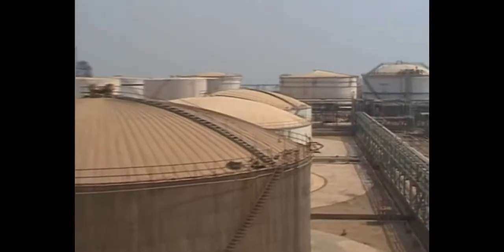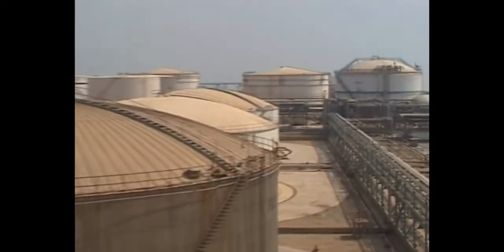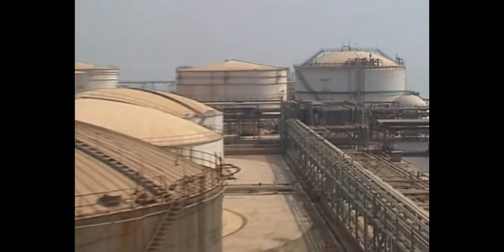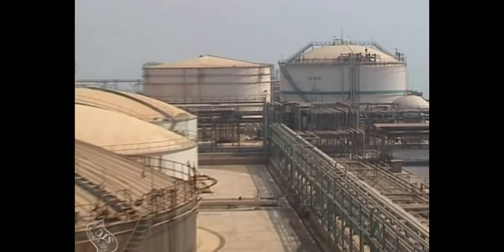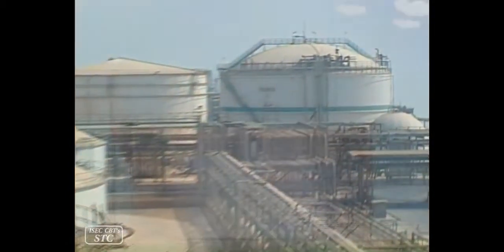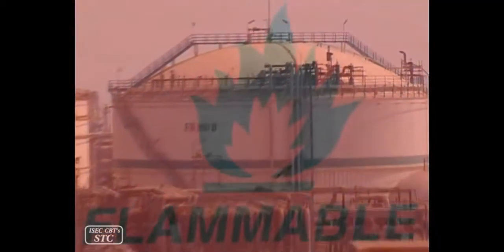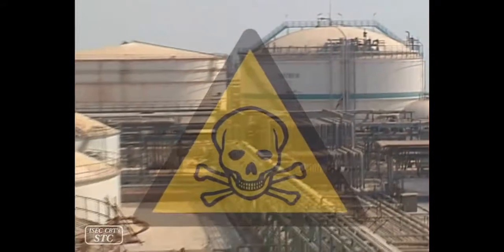Fixed Roof Tanks. This type of tank is used for the following cases: 1. The vapor pressure of the stored fluids is low or trivial. 2. The subject material is toxic or inflammable, or its purity is of great importance.